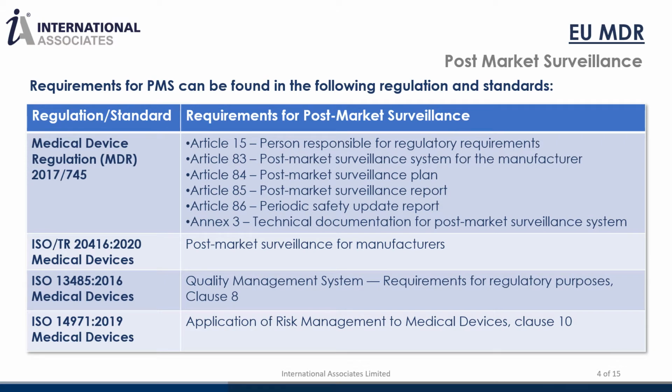Therefore, we can say that PMS serves to identify problems in the design of the product and the use of the device after it is placed on the market. There are several MDR articles that describe the requirements, which are further supported by the ISO standard 13485 and the ISO standard for risk management.